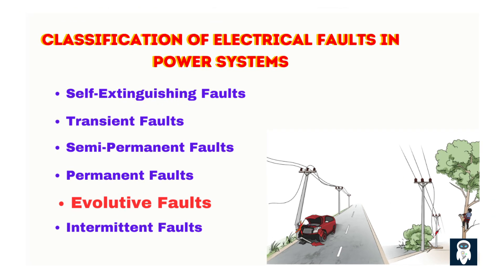Evolutive faults begin as single-phase faults and gradually escalate to involve multiple phases, often due to progressive deterioration of system components. They are initiated by minor insulation issues or mechanical stresses and gradually worsen, causing cascading faults that require prompt intervention to prevent further escalation. An example is aging insulation deteriorating under load stress, leading to multi-phase arcing faults. These faults are potentially catastrophic if undetected and highlight the need for regular system monitoring.